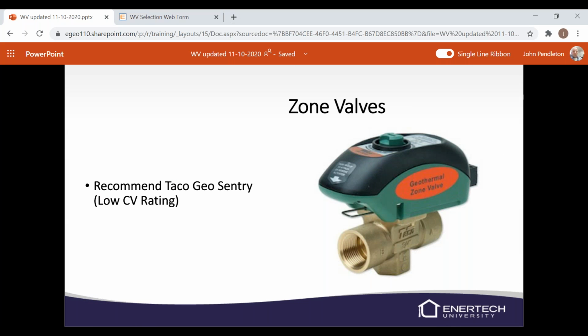Zone valves, we recommend using these Taco Geo Sentry zone valves for your radiant or your hydronic forced air zoning. They have a low CV rating and they're super reliable, so we don't have many problems with these at all. They've got a little light on there that'll tell you if it's open or closed, and you can also manually open these as well. You can remove the head very easily if you need to replace it. So we would highly recommend using these Taco Geo Sentry zone valves.